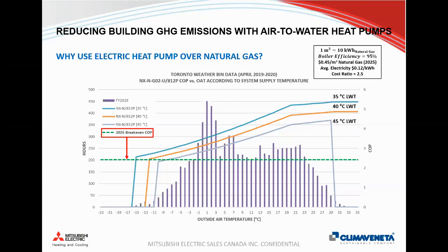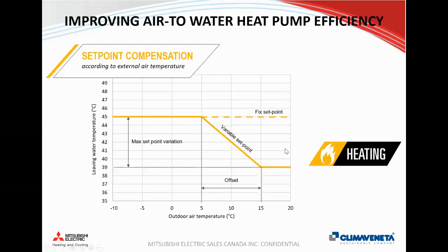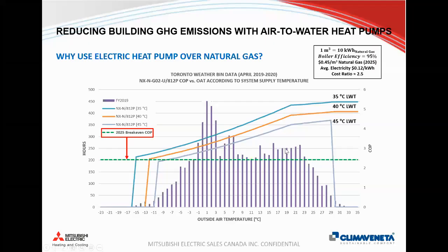Just the other point that I want to remind, we talked before about with air to water heat pumps, designing for the lowest supply temperature possible. So the example that we looked at before with a 45 degrees Celsius supply temperature shows your heat pump COP over outside air temperature like this. But for the same capacity, but using a lower water temperature of 40 degrees, you have a higher efficiency, meaning depending on the number of hours that you're operating at, this translates into higher savings.